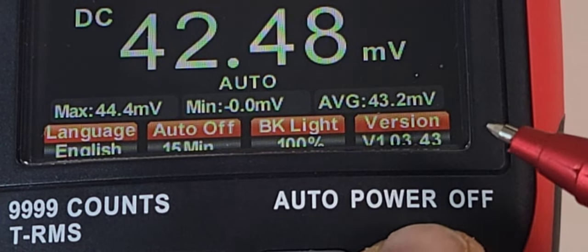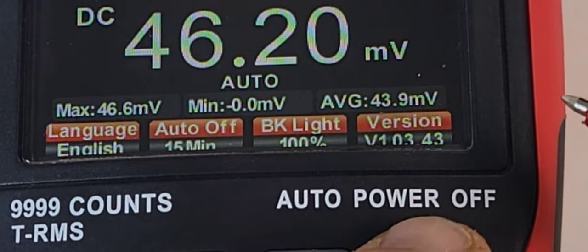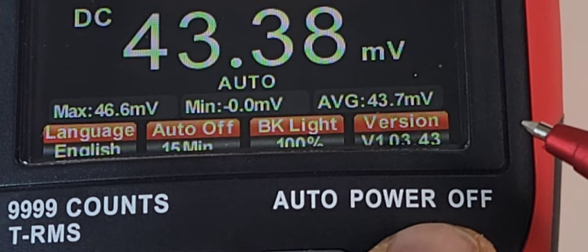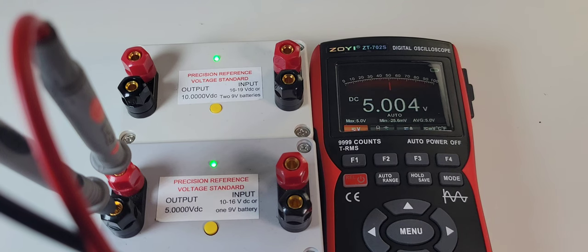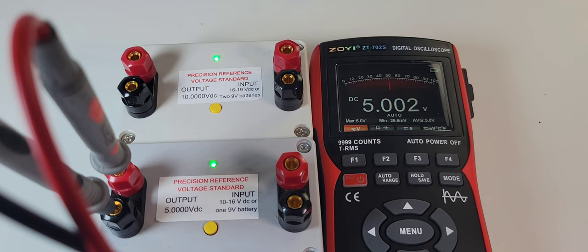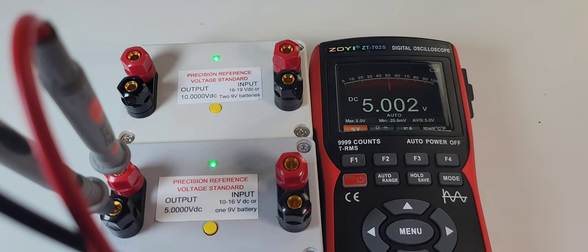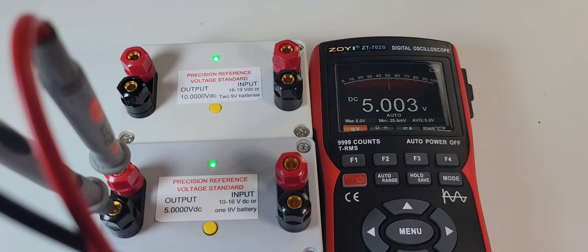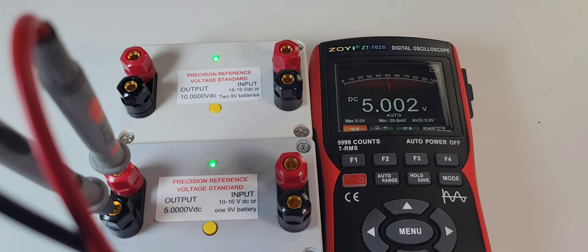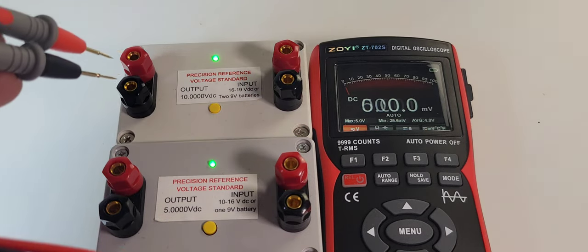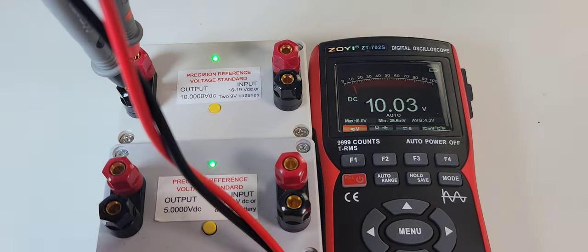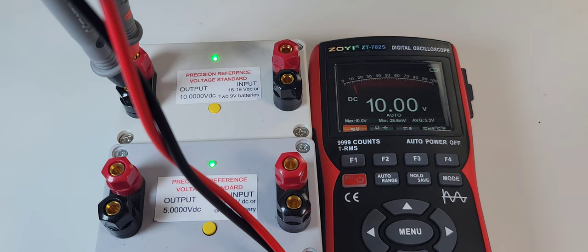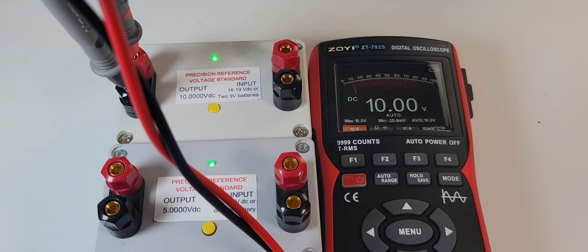DC precision voltage time. I have a couple of voltage reference standards out here, thanks again Fred Chu, Amazing Tech. 5.000 volts is what we want. 5.0032-ish, definitely in spec. Let's try the 10 volt and are we gonna get 10.00 volts? Oh it is so close, it is so close. It is hovering back and forth, so yeah just about there, almost nailed it but not quite.